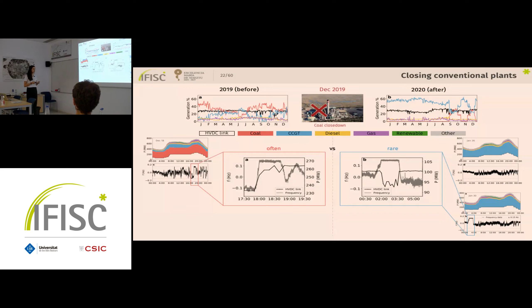So it has a kind of threshold control that is only activated when the frequency reaches plus or minus 0.15 Hertz. There is a difference though between the case before the close down and after the close down, and that is that before the close down, the frequency fluctuations were much larger because coal was then the main generation source, and so the control from the link was activated quite often. However, nowadays this is happening less frequently, and moreover, when we see that happening, the reason behind these frequency excursions in the first place is not recorded in the power data. So we cannot find any power change in the data that could lead to this frequency fluctuation. So we believe this is some kind of correction measure from the grid operator or something like that.